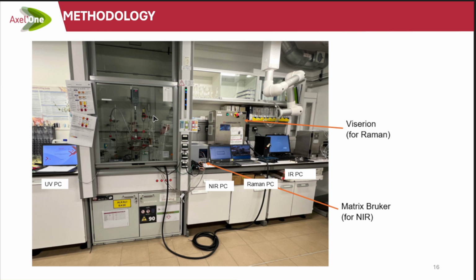The nice thing about some of these techniques, contrary to infrared where you had to have the system really close to your reactor, is that for others like Raman or NIR, you can have long fiber optics. So in our case, the equipment we get, we always manage so that we can go to the industrial site afterwards to validate all the things we've done in the lab. Our instruments are really sometimes the exact same ones we're going to use at the factory plant or pilot scale plant to validate the final models.